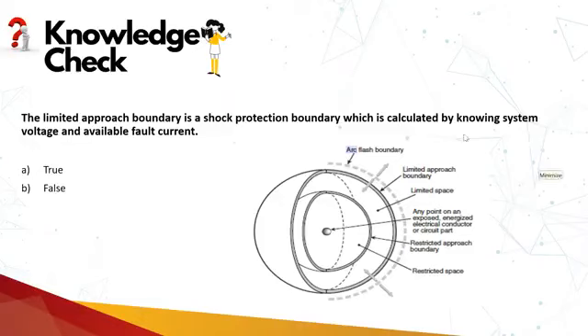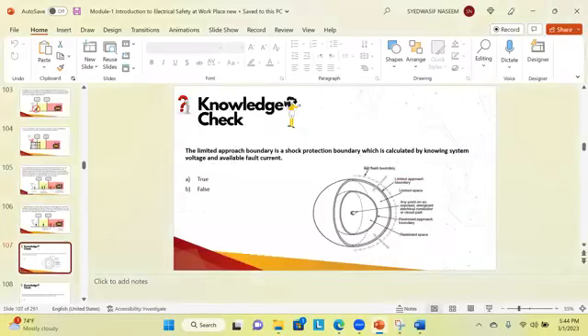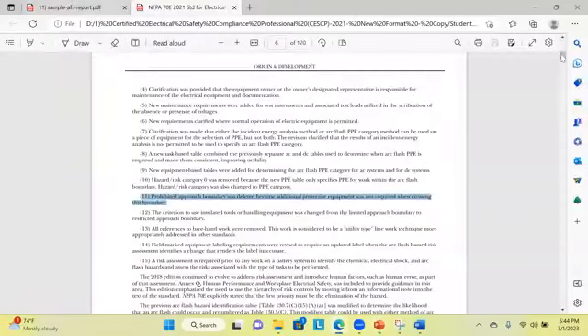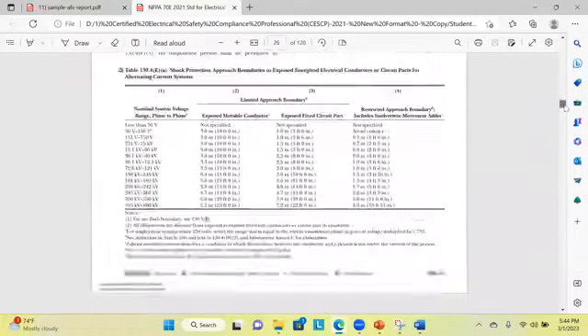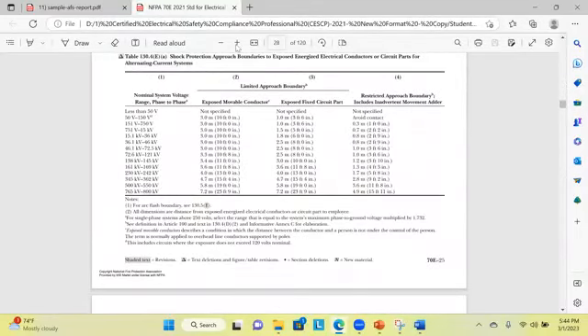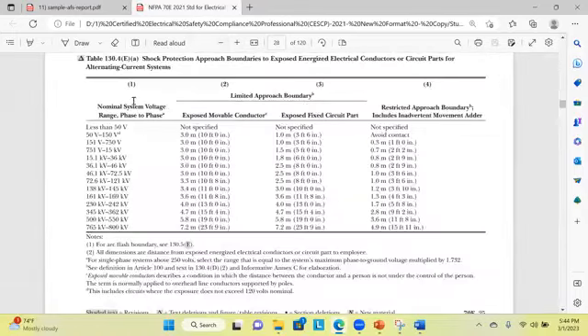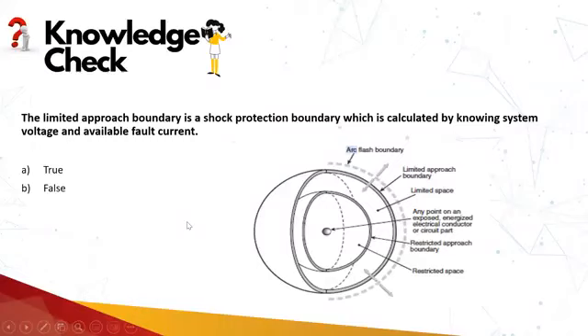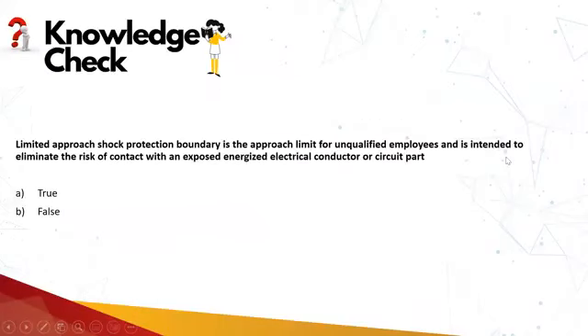The answer to this one is false, because for the limited approach boundary or the restricted approach boundary, which is basically part of the shock protection boundary, if we know the voltage, we can do it. There is no requirement of knowing the fault current. If you look into this table again, yes, this one, we can calculate the limited approach boundary and the restricted boundary if we only know the voltage level. So there is no requirement of knowing the fault current. Okay, moving to the next one.